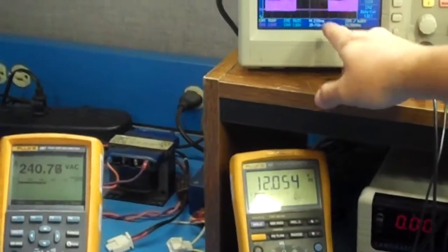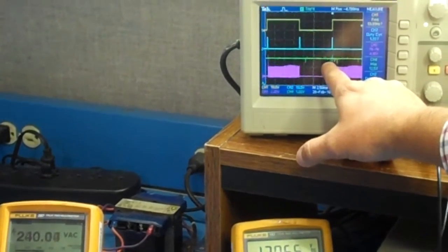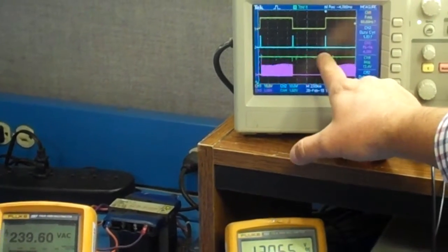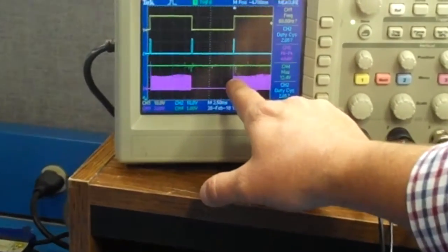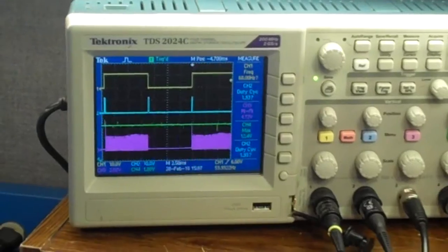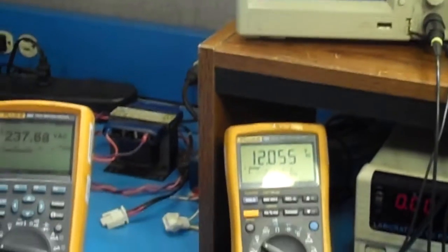So I'm going to ask Tony to slowly start dropping the voltage. The last thing I want to point out is that we have a little bit over 2 divisions for the initial pulse, and then a little over 1 division on the sustaining end of the pulse string. Alright, so go ahead, Tony, and start.